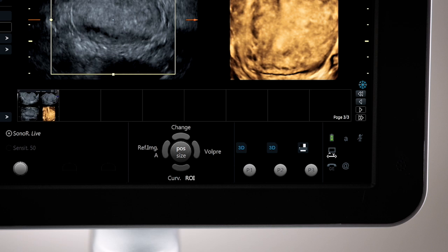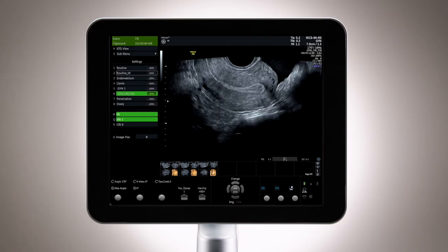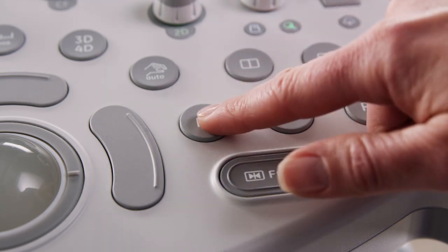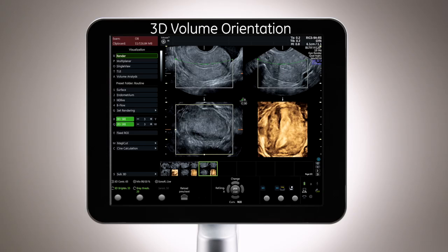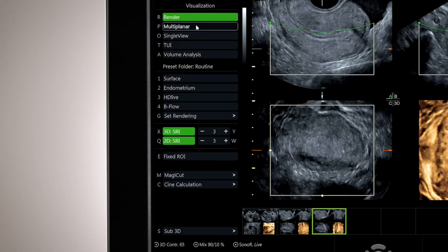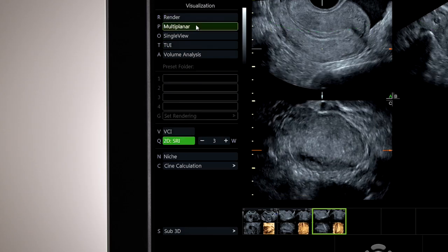Selecting the Freeze key, or Vol-Pre trackball key, will cause the system to return to a live scanning state, so it's important to store the volume as soon as the acquisition is complete. To concentrate on the sectional planes, remove the rendered image by selecting Multiplanar from the display menu.